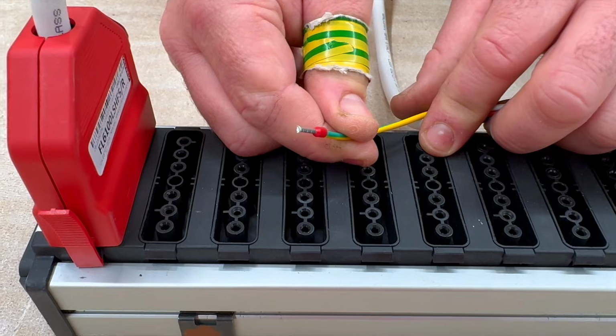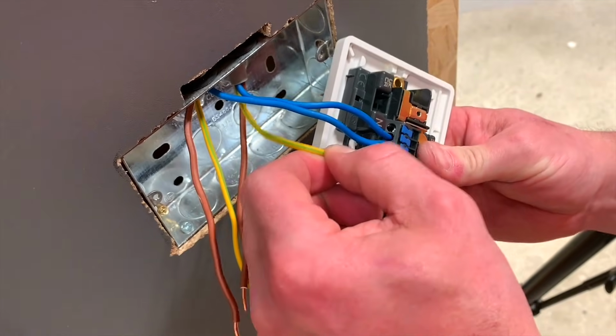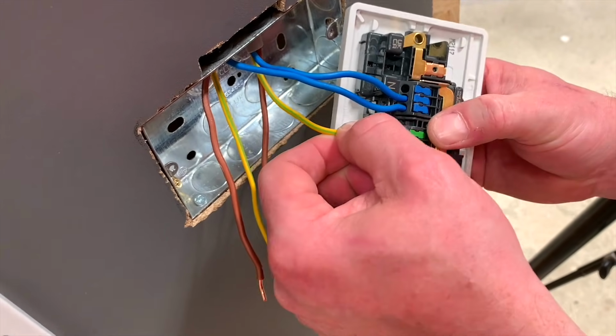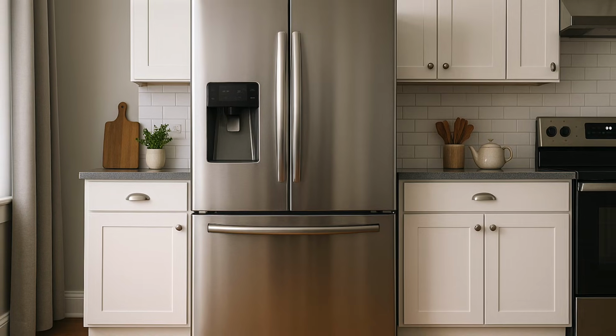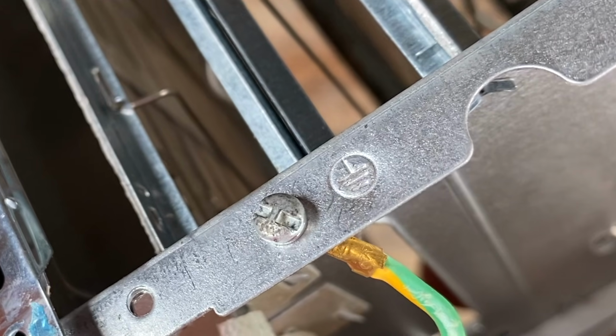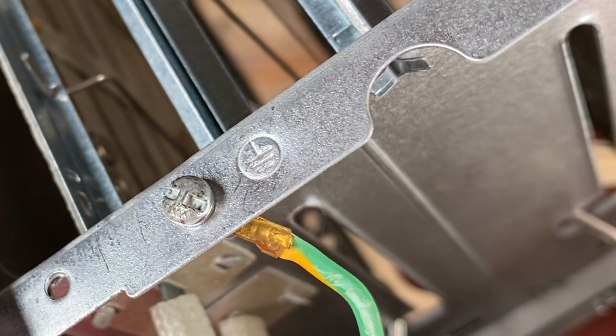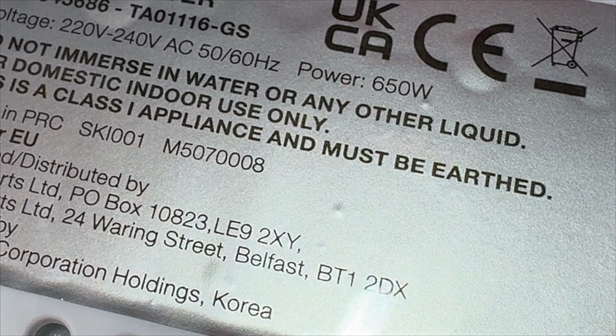So for this to work, the earth connection needs to be intact. The earth pin, the protective conductor in the flexible cable, and the internal earth connections must all be sound. Common Class 1 equipment includes refrigerators, washing machines, kettles, toasters, and electric radiators. Some appliances include markings like the earth symbol or the letters PE, but many do not.